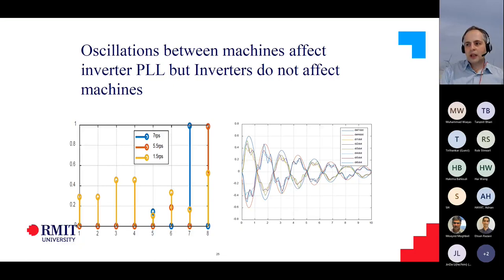We observed that the oscillations between the machines, or the modes between the machines—whether inter-area modes or even local modes—could affect the inverter PLLs. That means that if we have any oscillation in the system, that would go to the inverters and would impact their capability of providing that good reference point for the inverter controllers. Now, the other fact is that the inverters really do not impact the machines, so any dynamic in the inverter usually doesn't propagate to the machines. That's actually a good sign in a way, that we don't have that much coupling between the inverter modes and the machine modes, whereas the machine modes will really impact the inverter modes.